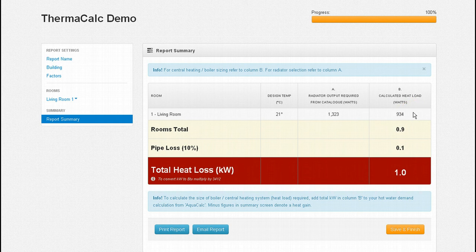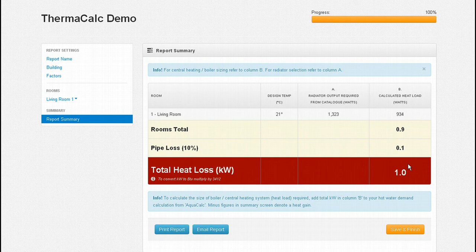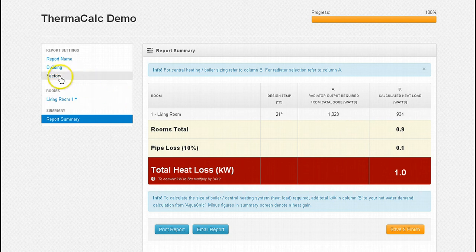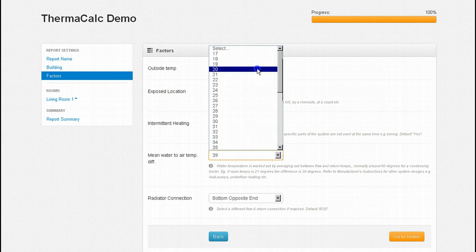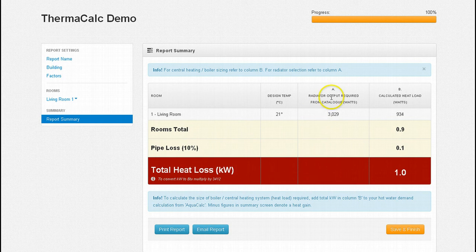Our living room requires 934 watts or 1 kilowatt including pipework losses from our heat source for space heating. You may notice that for heat pumps and underfloor heating designs that require a lower mean water to room air temperature F1 factor, your calculations are considerably greater in column A than those for a traditional radiator type installation. This makes sense when you consider the lower radiated surface temperatures for these systems. ThermaCalc is really flexible so have a go at playing around with the figures. For example, if we wanted to change our design to reflect an underfloor heating system we would select a lower emission factor from the report settings tab on the left, and straight away a larger calculated output in the summary screen is generated in column A. Experimenting this way lets you quickly see the effects that different heating systems have, allowing you to accurately design, specify and adapt to new plans at any point of a project.